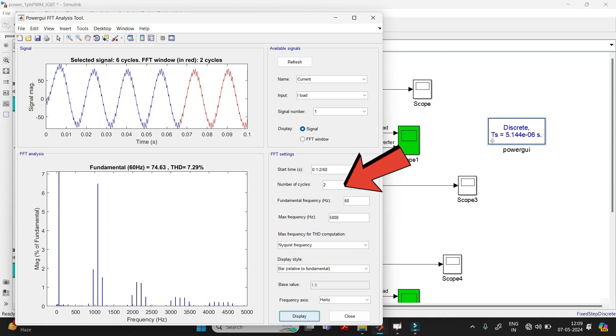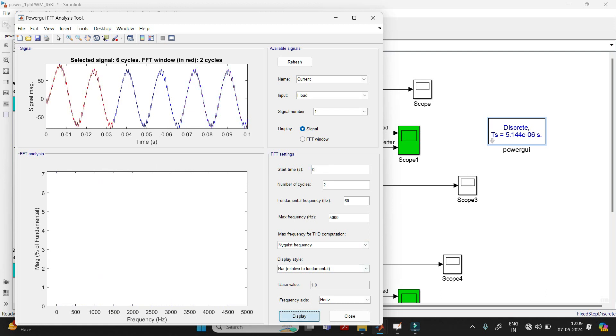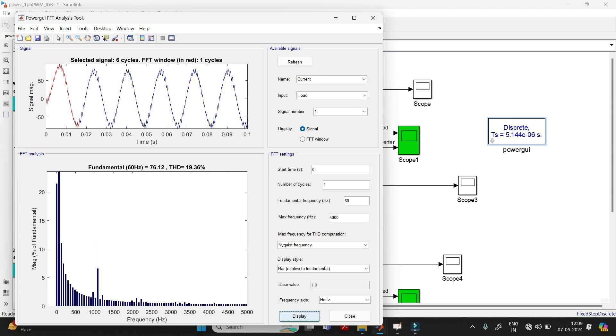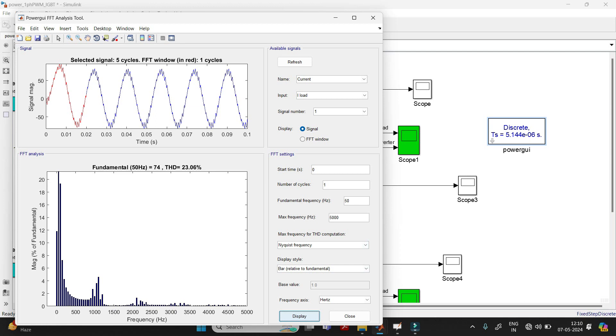In the FFT settings, if you give the starting time, it will compute from that point. For example, if you give 0, it starts from 0 and covers 2 cycles. If you want only 1 cycle, set the number of cycles to 1. The fundamental frequency here is 60 Hz; if you want 50 Hz, you can change that too. These are the settings you need to know.